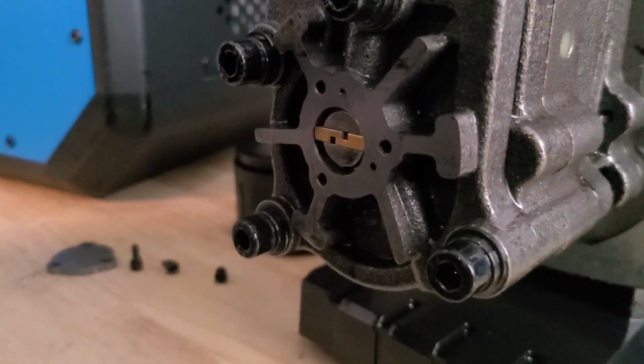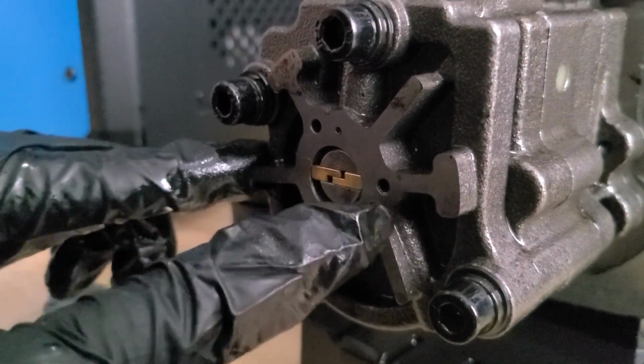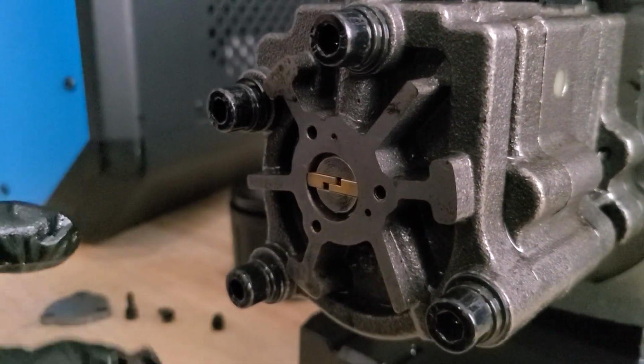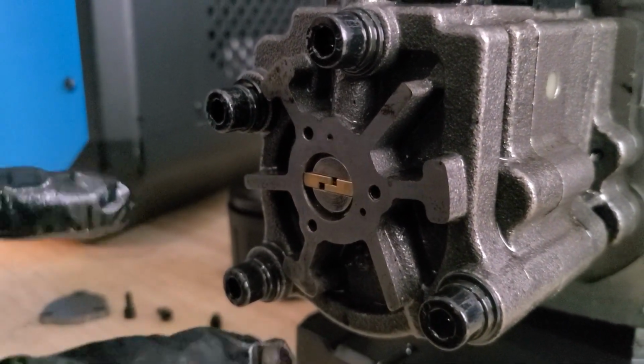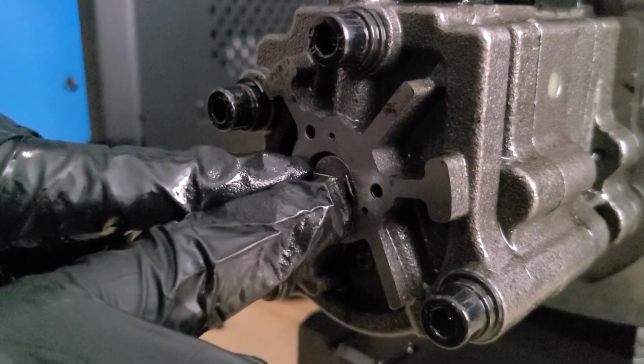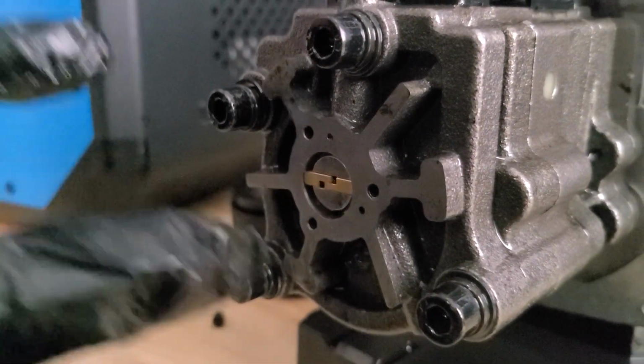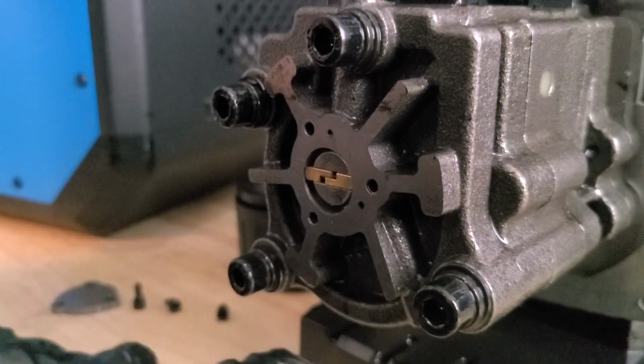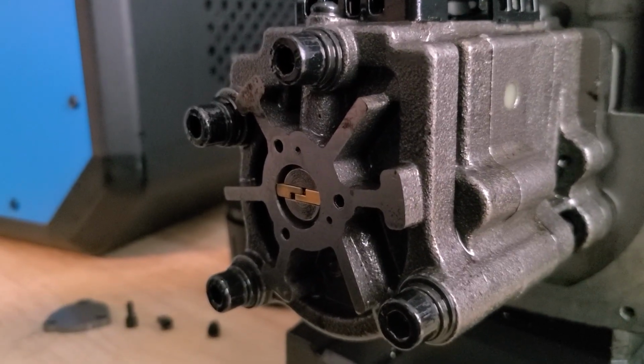The biggest problem we see with the brass wipers is if there's not a big enough gap between each wiper, there is a small spring between, and you want that spring to get activated. And you know it's activated if there's a gap between holding the wiper against the wall. If your brass wiper does not look like it has a gap, at that point you will want to get a new brass wiper for your vacuum pump.